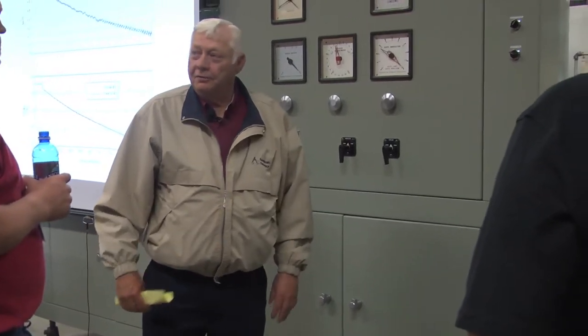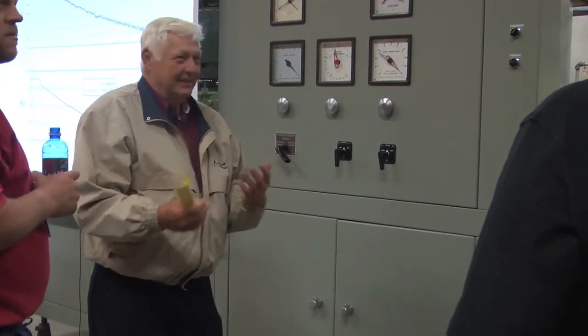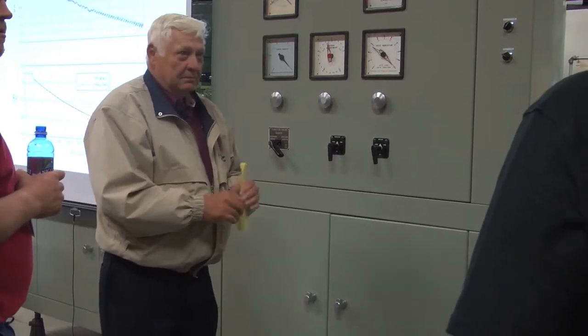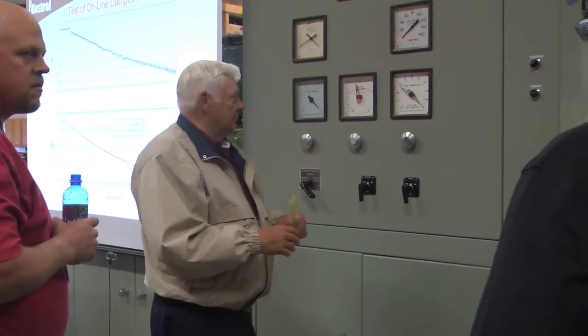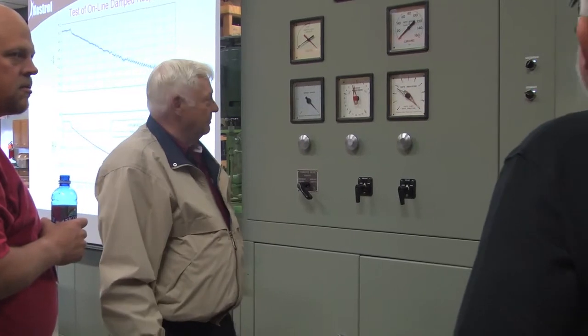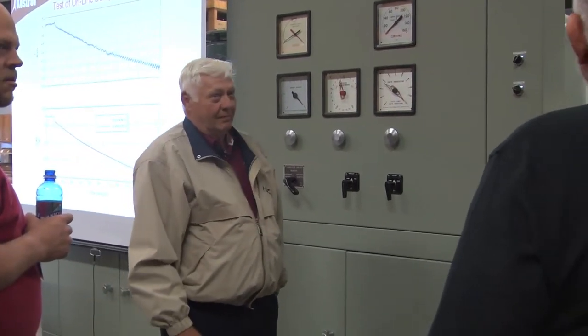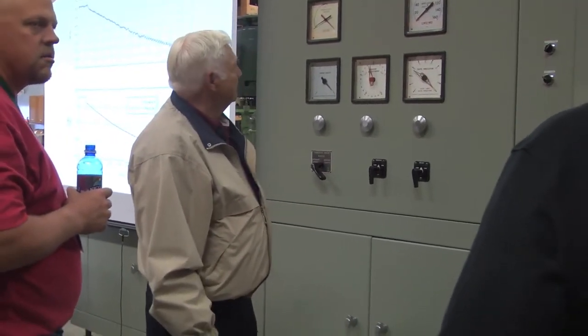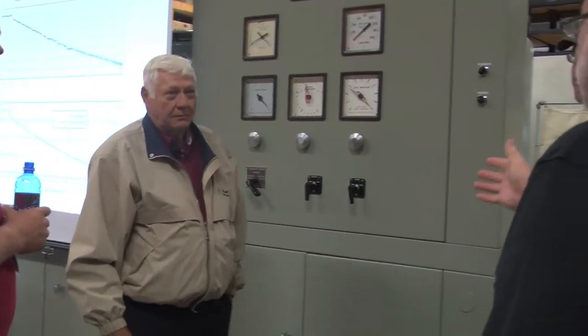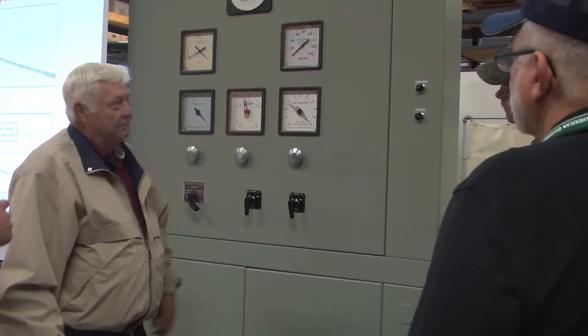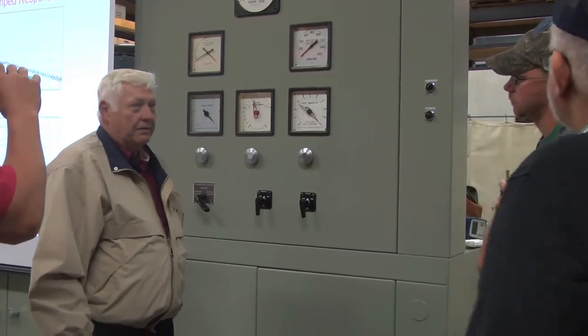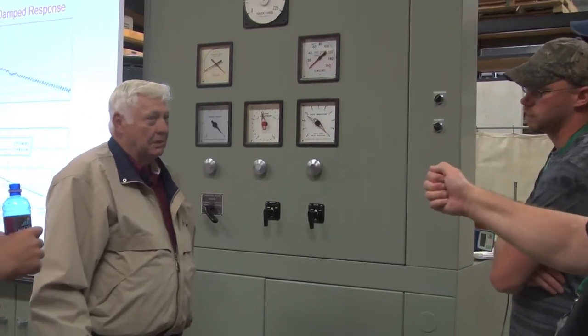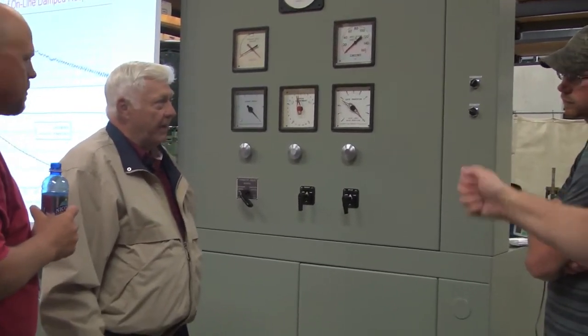See, on a mechanical, depending on gate timing, it can take up to 10 minutes on an impulse turbine to make a change. On a Francis, usually 5 minutes or so will do it, but I've seen them from 5 to 7 minutes. We've timed them. We're still not there yet. If that guy's giving it a set point, I think 4.5, 5 minutes.